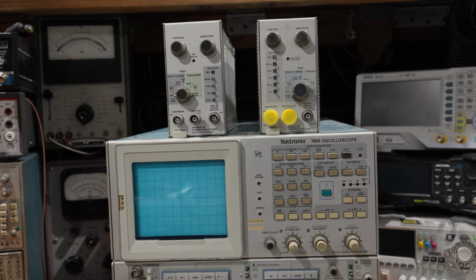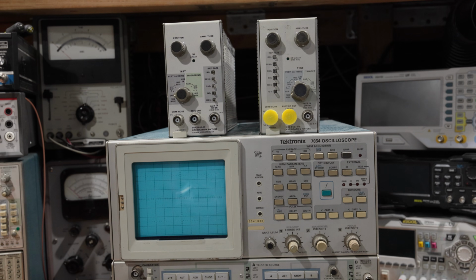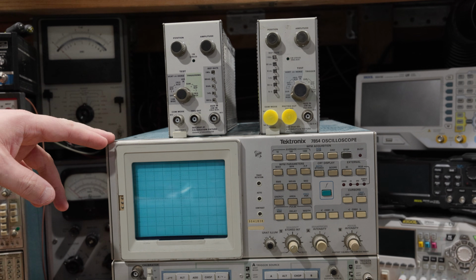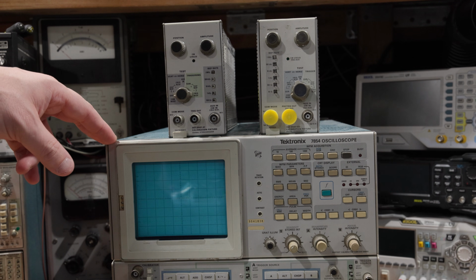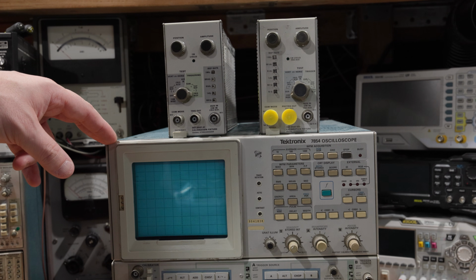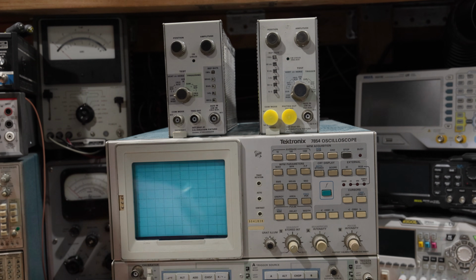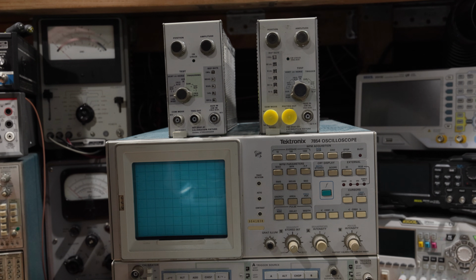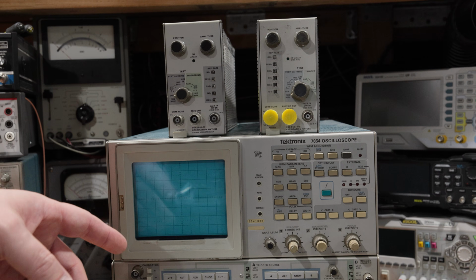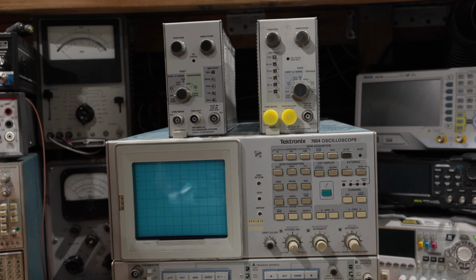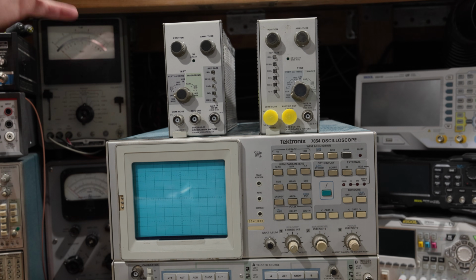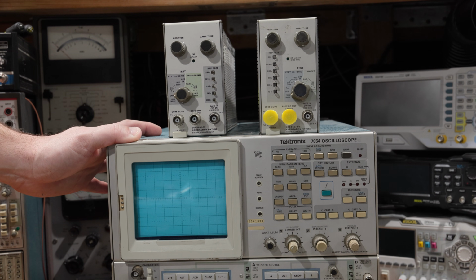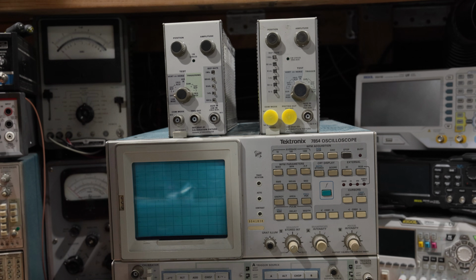There's even a test card that goes along with this that I'm in the process of rebuilding. I'm going to attempt to do a calibration on this frame without it. The test card's function, it's used in one of the steps of the calibration process. It takes everything back to analog. All the digital stuff gets pulled out, and it does a thermal balancing between channel 1 and channel 2. It switches between them rapidly, and you can do a thermal balance adjustment. So, incredibly detailed calibration and alignment procedure, which we're about to undertake.